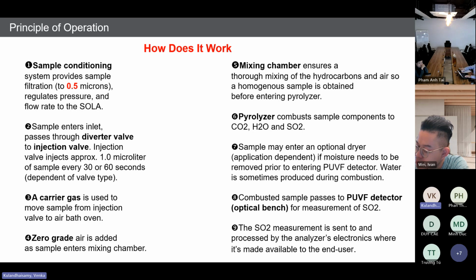Okay. So whenever the combusted sample is passed to the PUVF detector, the detector has a UV lamp. That UV lamp emits UV light at a particular wavelength. That particular wavelength of UV light will energize the SO2 molecules. Okay, it will energize only SO2 molecules. Whenever the SO2 molecule gets energized, it then has to de-energize, and whenever it de-energizes, it will emit photons. Photons means light energy.